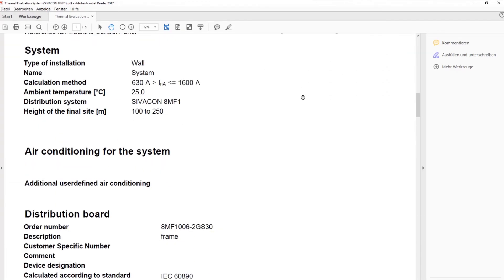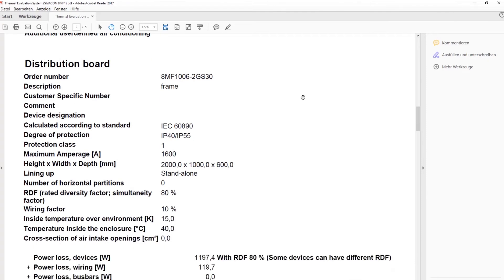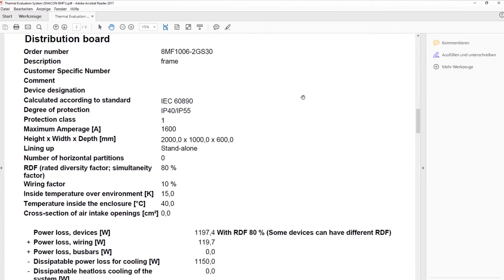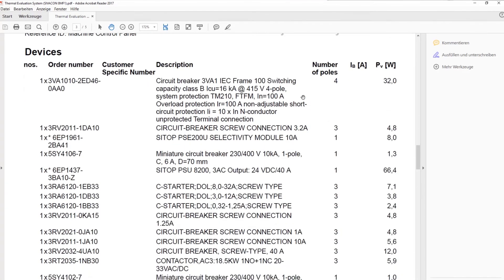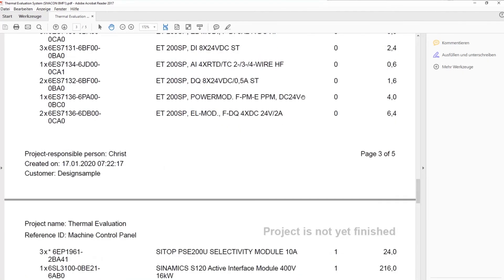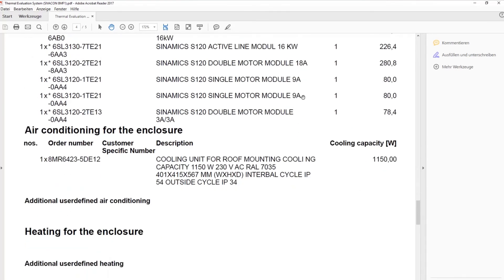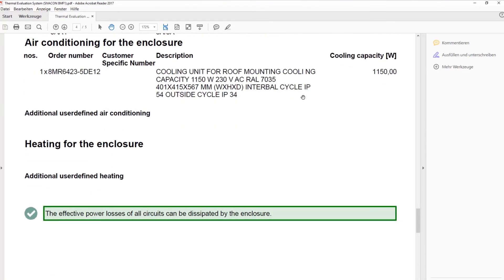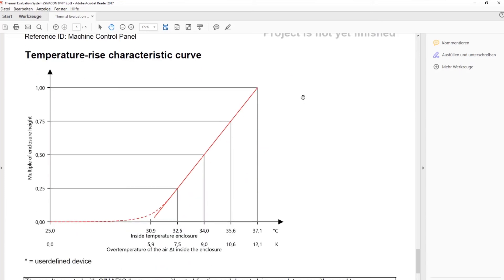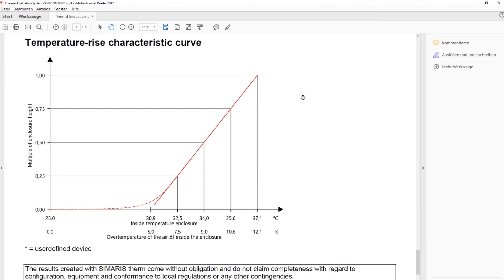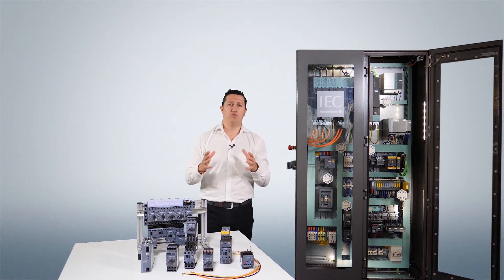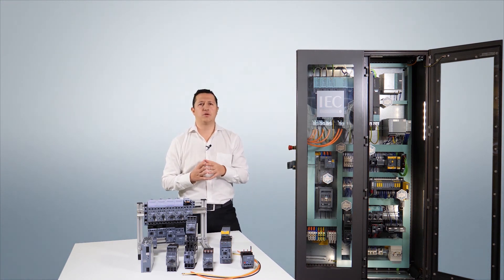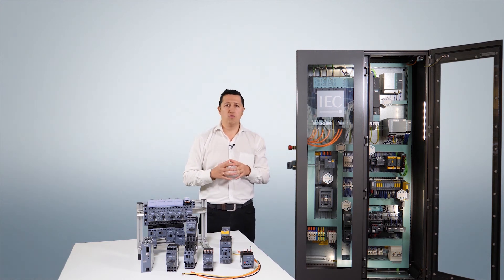Based on the power loss data already stored for typical Siemens control panel equipment, the tool calculates the power requirement in line with the defined preconditions. SIMARIS therm proposes suitable cooling and heating device lists for use inside the control cabinet, based on individual general operating conditions, device-specific power loss values, and consideration of implemented load balance in combination with installation height. The calculation results and reports can be used for verification of temperature rise limits in accordance with IEC EN 61439-1.